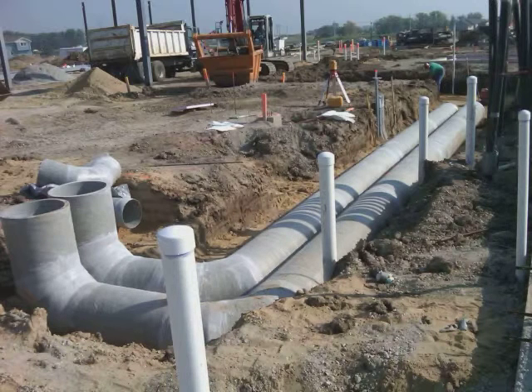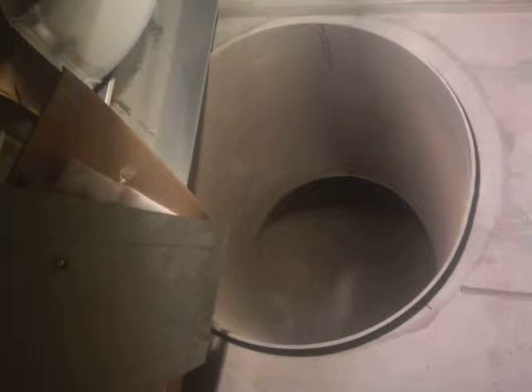Was it difficult or challenging at all to transition from the fiberglass to sheet metal? No, it was relatively easy. Kind of the same concept as regular sheet metal transitions, and the fire dampers had round collars on them, so we just slipped the round collars inside the FRP. We fastened them with sheet metal screws and then continued on with sheet metal.